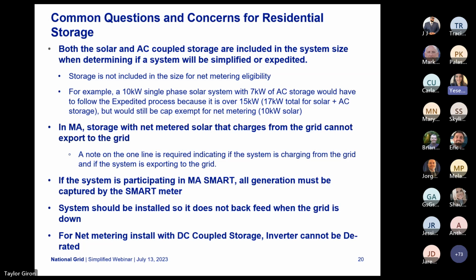If in MassSmart, storage with net metered solar that charges from the grid cannot export to the grid. So please keep that in mind. If the system is participating in MassSmart, all generation must be captured by the MassSmart meter. The system should be installed so it does not backfeed when the grid is down.